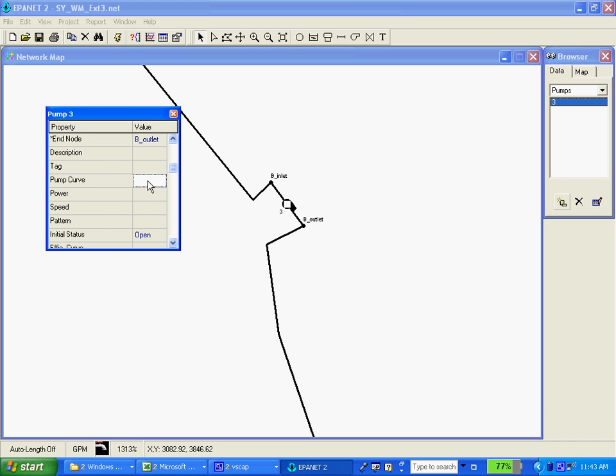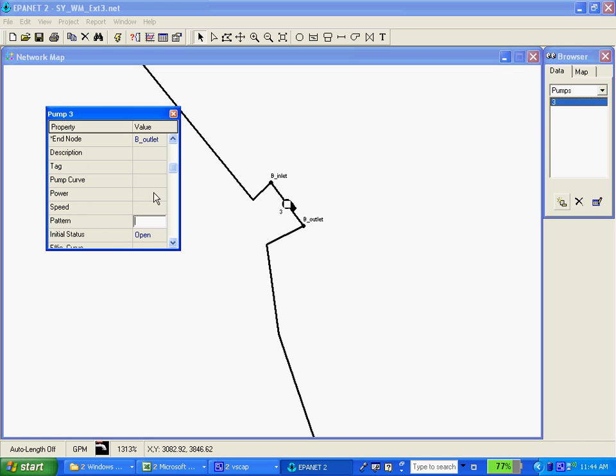Here's the pump curve which I'll go ahead and enter in my next step. Notice there is a section here for a pattern to be entered for the pump. Be careful of that. I've accidentally put a pattern in for a pump and it can cause a lot of problems unless you intend it to be there. For instance if you put a community peak flow pattern in there unintentionally you can end up with some real bizarre results on your model. So for a simple model like this where I'm not actually doing any kind of variable speed I'm not going to be entering a pattern on the actual pump.